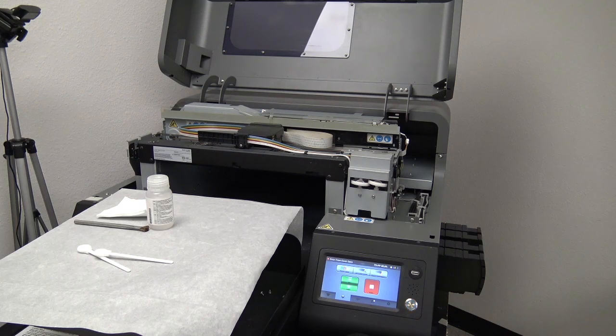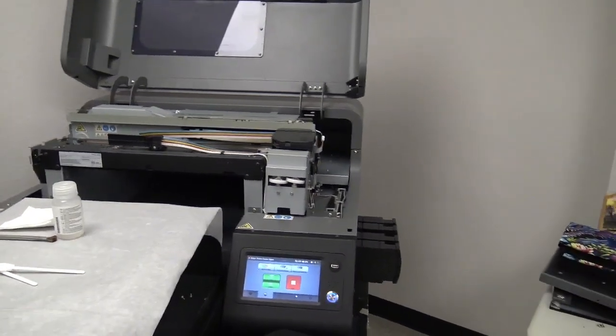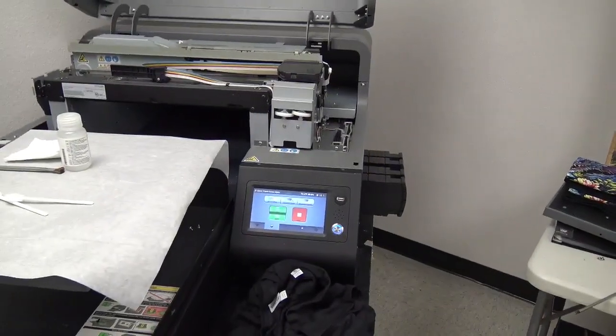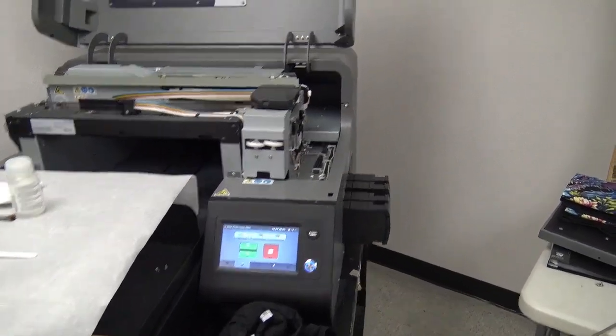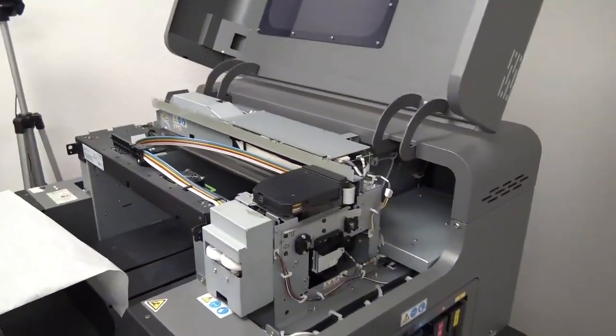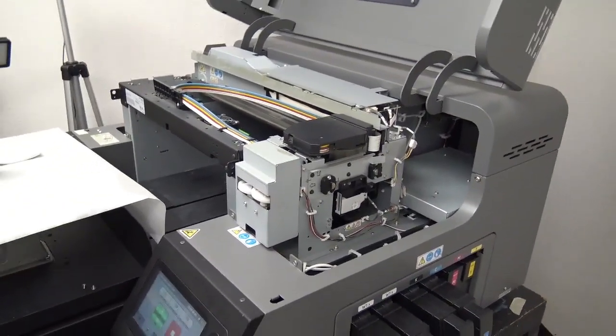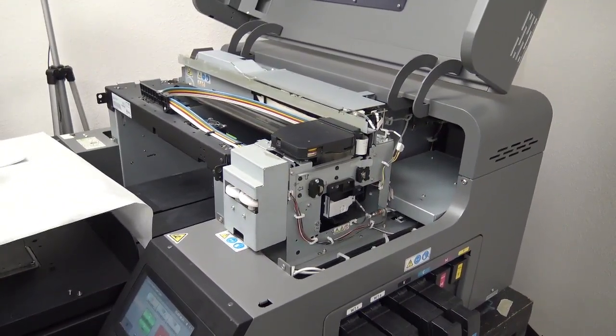And I'm going to show you guys how to manually release that carriage. Now, if you need to manually release it, that's because you might have an error code 999. If that's the case, please don't forget to contact RICOH Tech Support, start a case, have them help you troubleshoot. You don't want to void any kind of warranties by changing parts on your own. This video here is just for reference sake and showing you guys how to clean out your maintenance station. Okay, as you can see, my carriage is over here, back to its home position or over the maintenance station. I'm going to go ahead and power off my unit, and then I'll show you guys how to manually remove it.